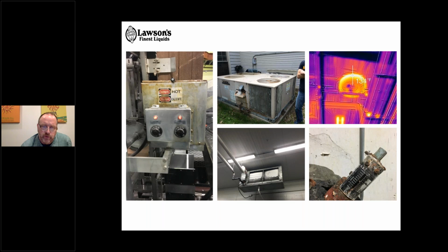Efficiency Vermont has a great program for replacing throttled back pumps with valves and putting in VFDs. Instead of running full amps all the time and cutting it back with valve control, you put on a VFD and ramp the pump down to the RPMs you need. They have great software to calculate the savings, and the investment in VFDs had incentives like $100 per horsepower, so they ended up costing us very little.